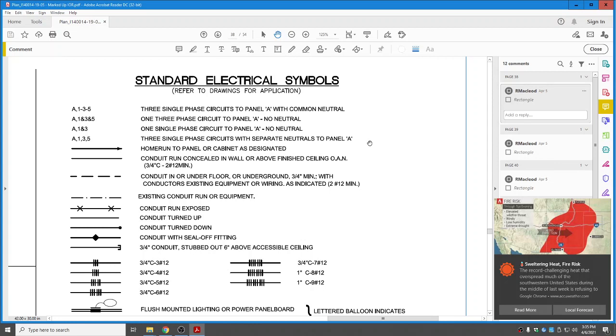And A1, 3 and 5 is a 3-phase circuit to panel A, no neutral. And A, 1 and 3 is a single-phase circuit to panel A with no neutral. And A, 1, 3, 5 is 3 single-phase circuits with separate neutrals to panel A. A straight line with an arrow at the end designates a home run to the panel or cabinet as designated.